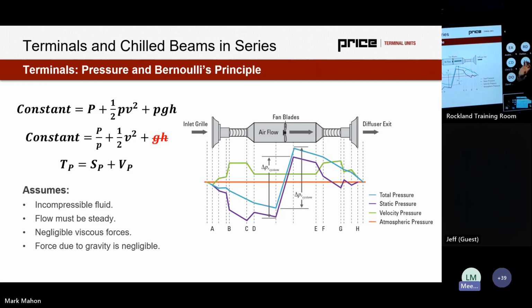So the rationale is that we're going to have a constant pressure, irrespective of if it's dynamic or if it's static. So whether it's pressure associated with the movement of fluid or pressure that's associated with a static fluid in a container, we're going to keep some consistency, assuming that it's not a compressible fluid, assuming that flow is steady, assuming there's negligible viscous forces. So the rationale here is an inlet grill condensing through a smaller piece of ductwork means we're going to have a static pressure drop and an increase in velocity pressure. A fan is going to both increase the dynamic pressure of the system. So we're going to have that air moving faster.